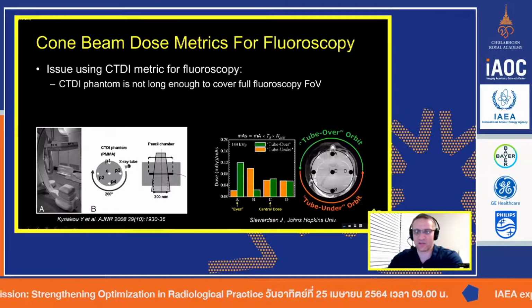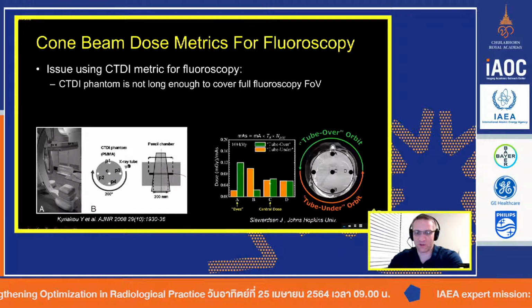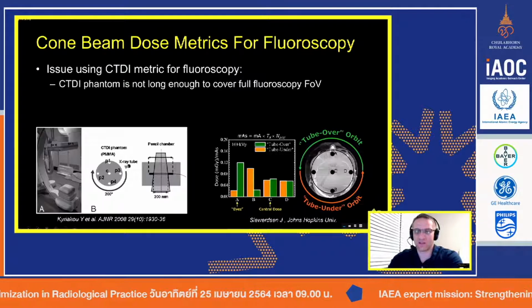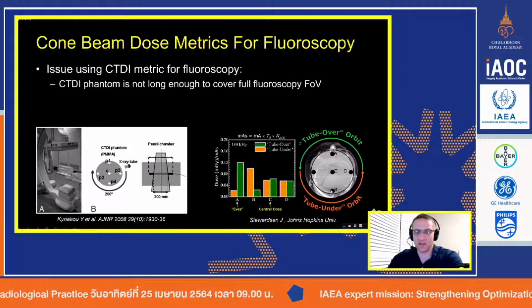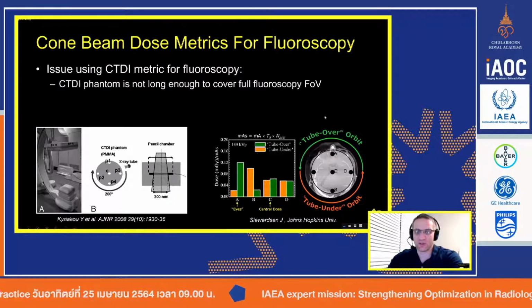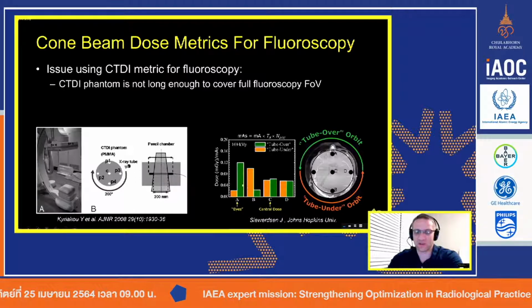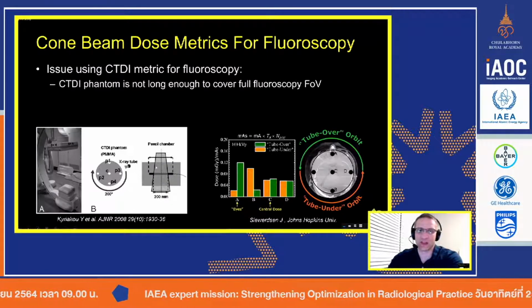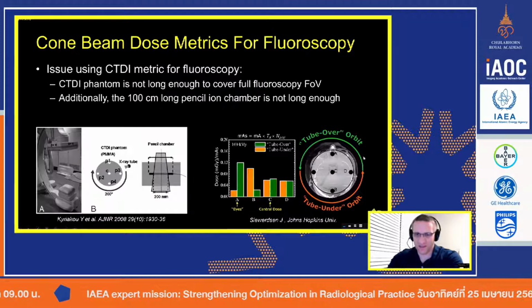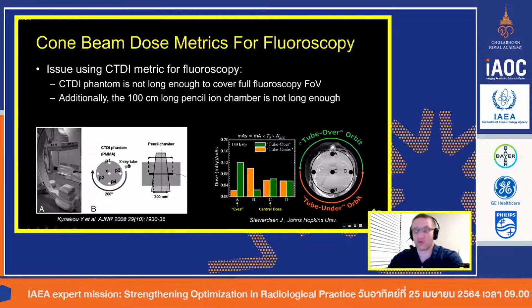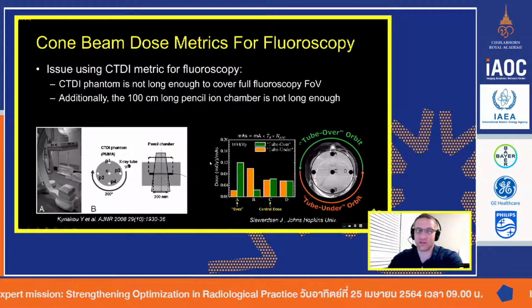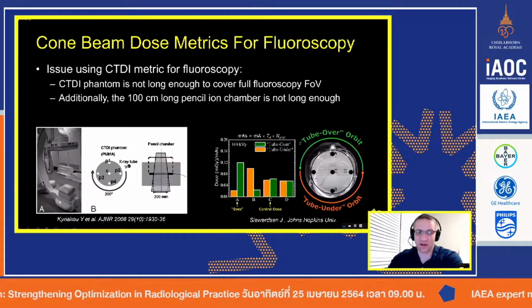So if you're measuring at the center, those are pretty much the same. But if you're measuring here, let's say at B, depending on whether you tube over or tube under, those values are completely different. And so when you go to make your calculations, where you place the ion chamber will drastically change the dose that you measure when you're calculating CTDI on this machine.